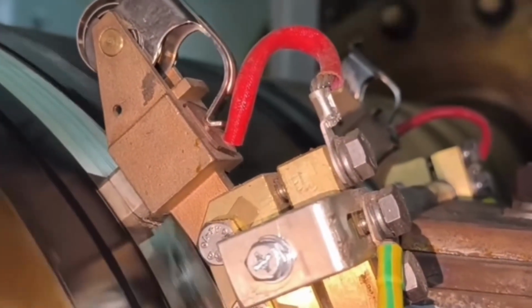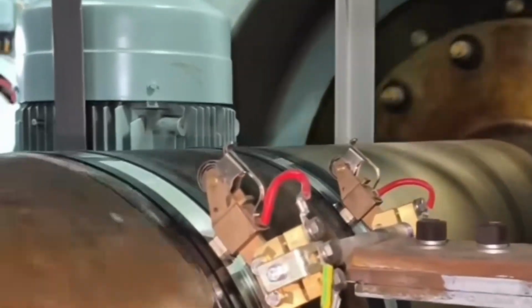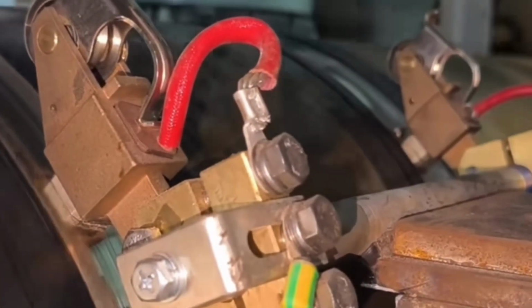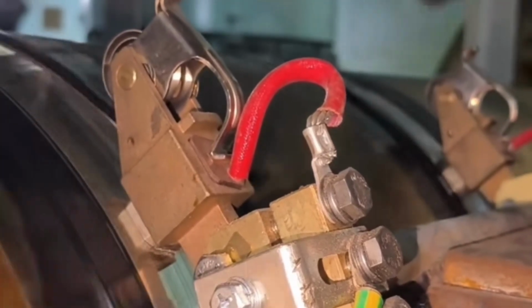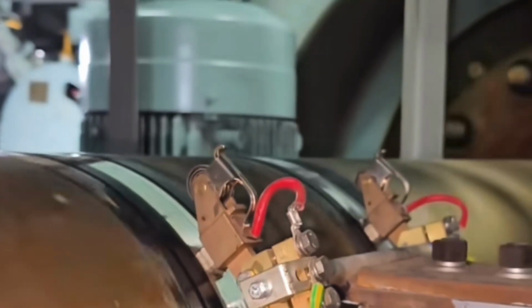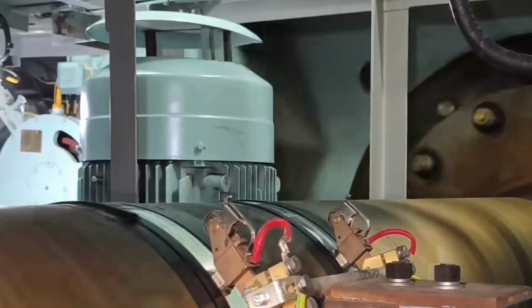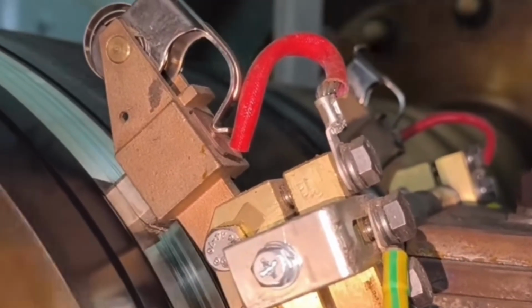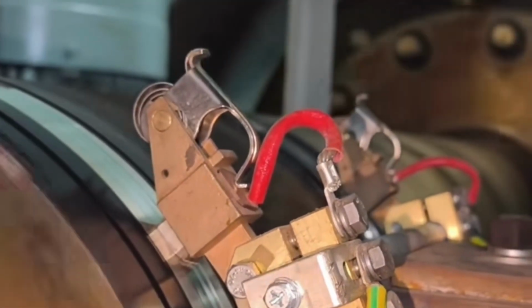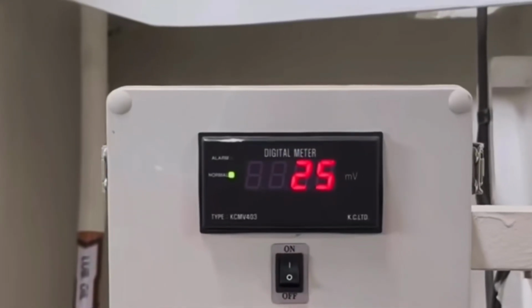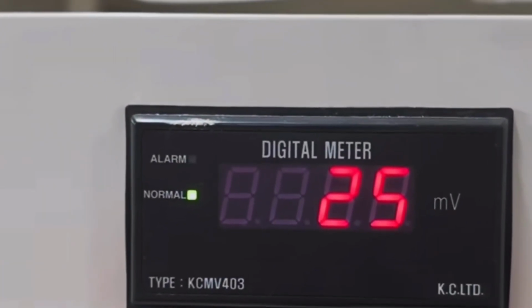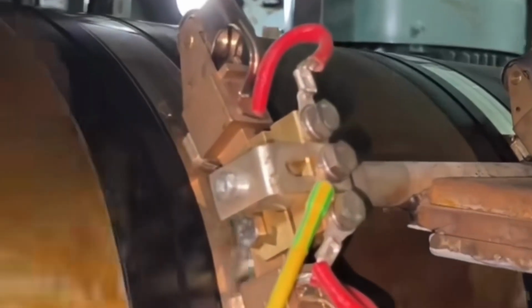Here we see the main engine shaft rotating, with the shaft earthing system fully operational. Notice the carbon brushes in contact with the slip rings, safely transferring electrical current through the red wire to the ship's hull. This prevents dangerous currents from passing through the bearings and protects the engine from damage. Each connection and every brush contact is critical. Keep an eye on how the system works in real time, ensuring the voltage remains safe. Now we can see the shaft voltage meter reading 25 mV, which indicates proper shaft earthing. This is a healthy value, ensuring safe discharge of electrical current from the main engine shaft. Proper earthing like this protects the bearings and improves overall engine performance, preventing costly damage.